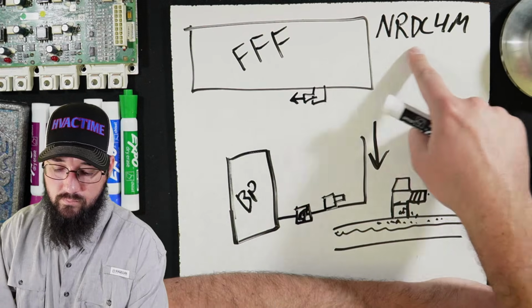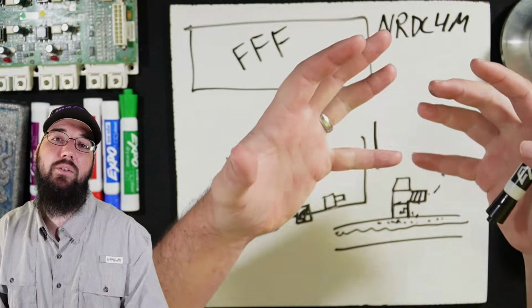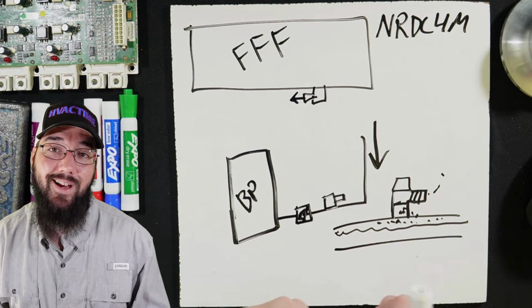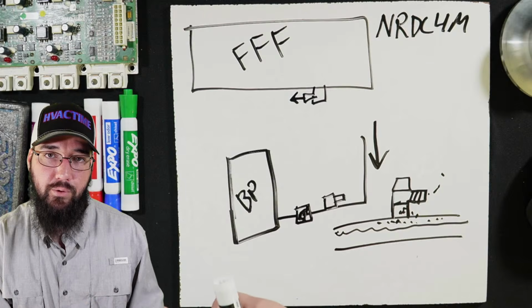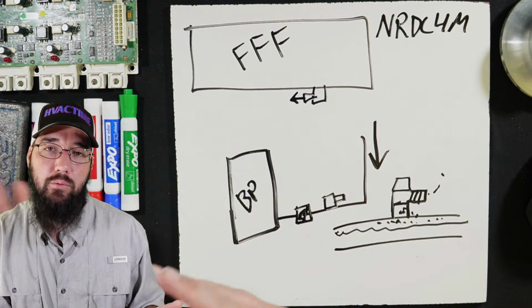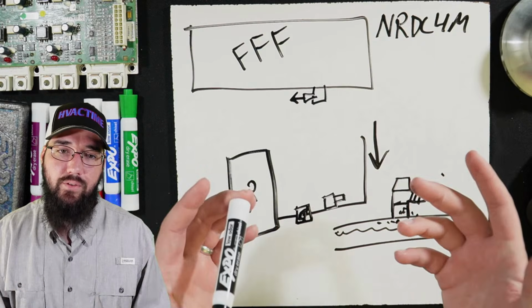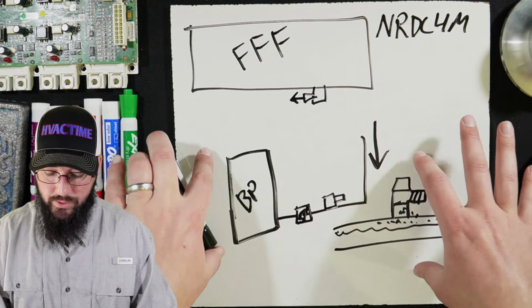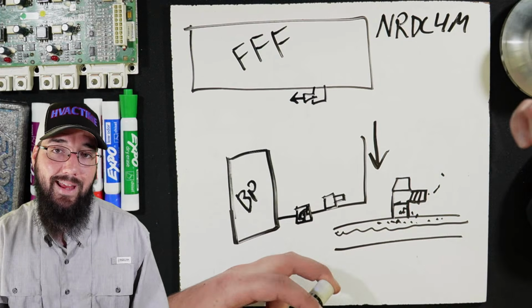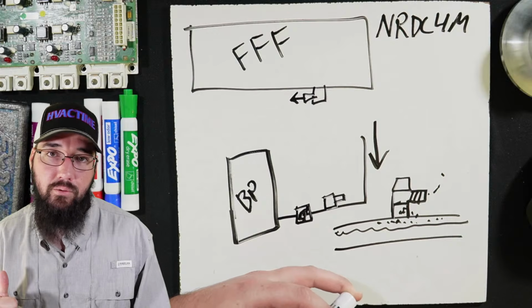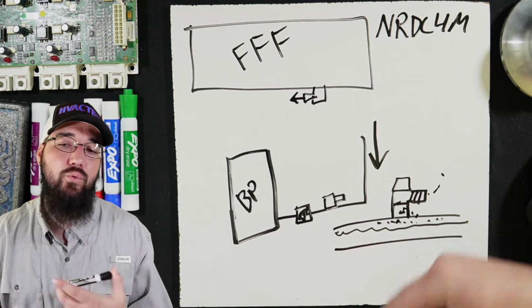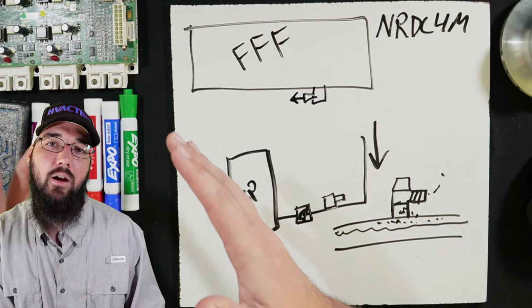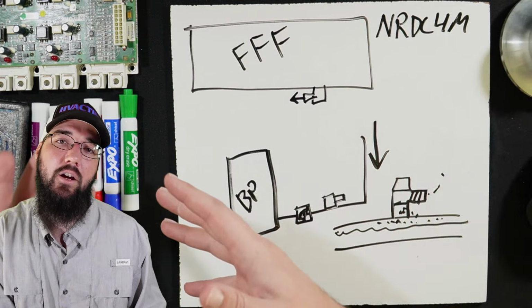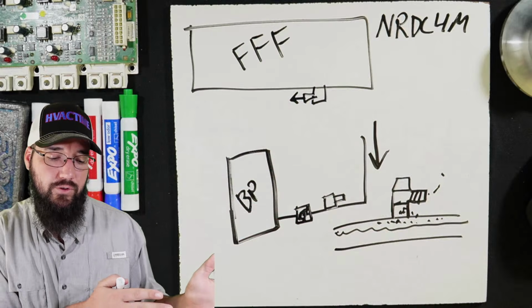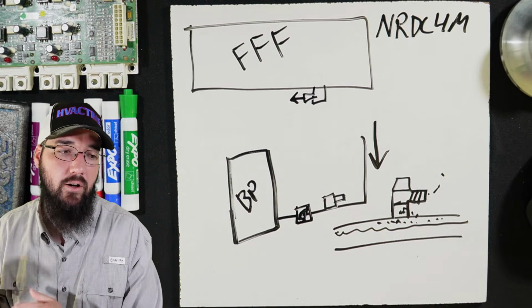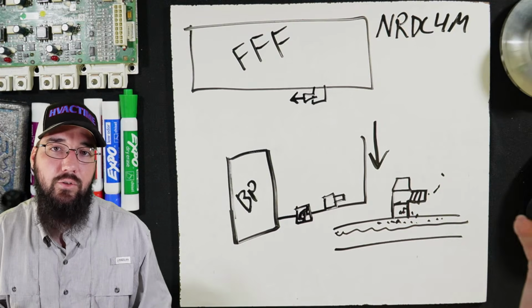Point is, this pump is incredible at pumping liquid refrigerant. It's designed to do so. They're not like a normal reciprocating compressor. These are actually designed so that you can move liquid refrigerant through them. Because of that, I like to use that pump on these types of systems, because what little bit of liquid I can get access to, I can just send straight through the recovery machine. I'm not having to reconfigure to get set back up for a standard recovery after already setting up for, say, a pull or something else. I'll just let the machine grab whatever liquid is there, and then you're just going to have to boil off the rest. It just is what it is.